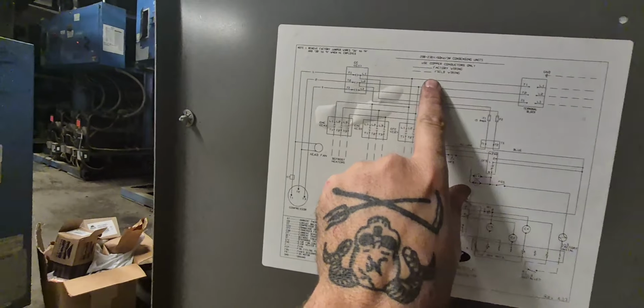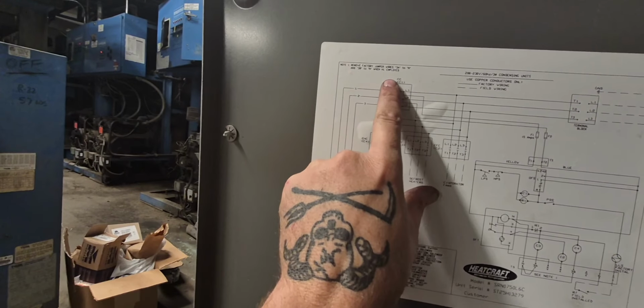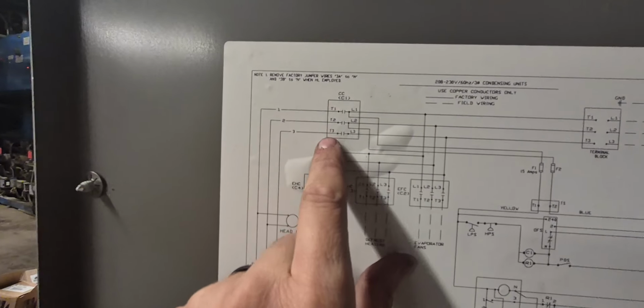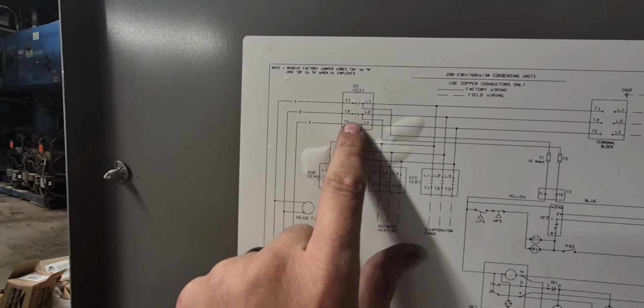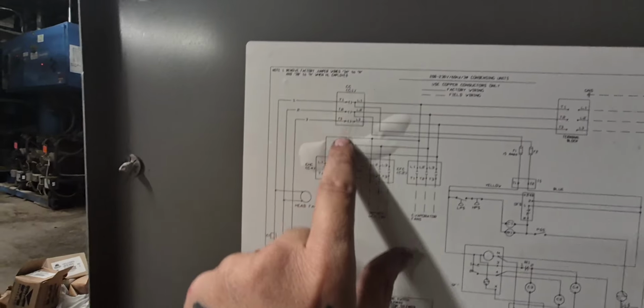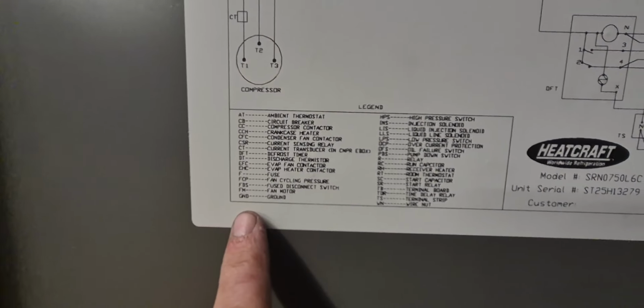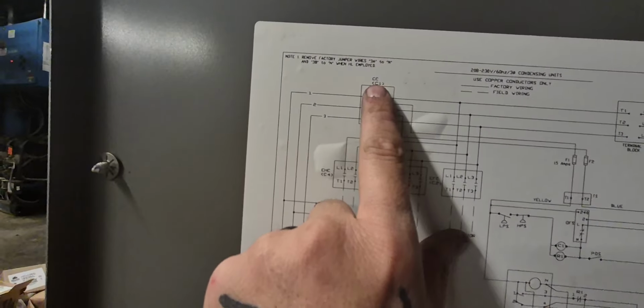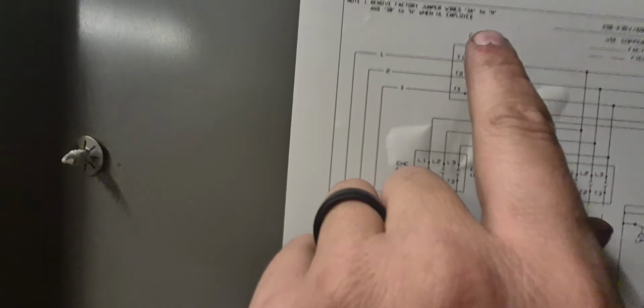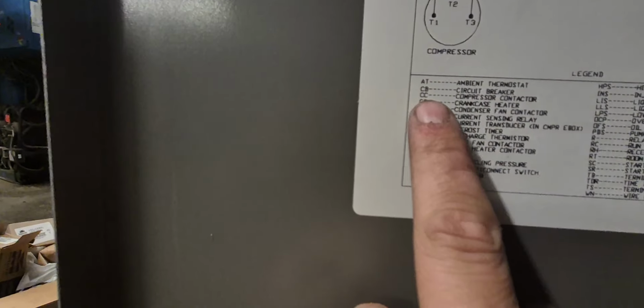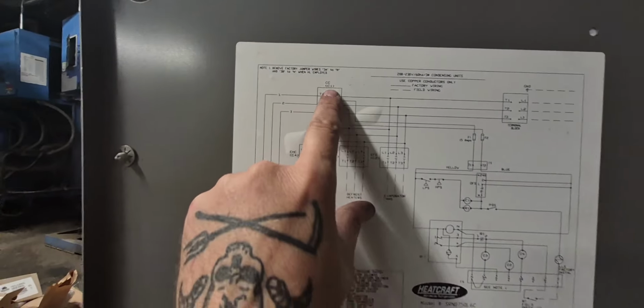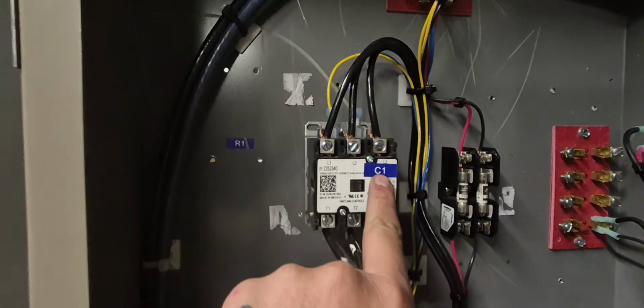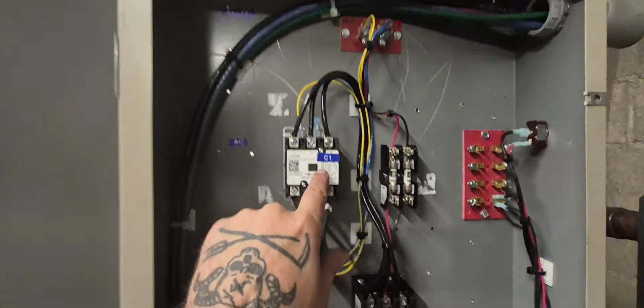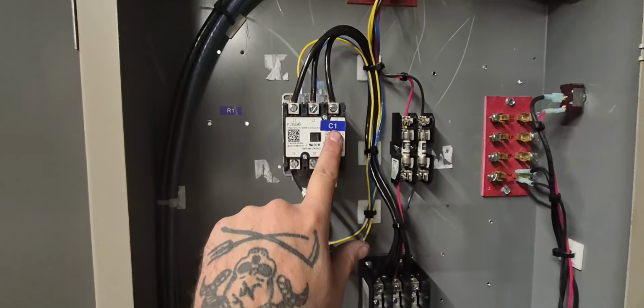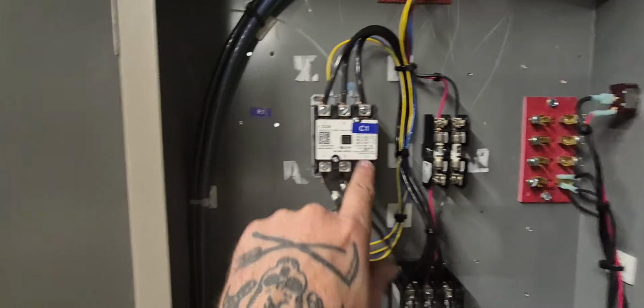And then if we follow those lines out, it shows it goes into CC1. So what does that mean? You can see we have 3 normally open points, but with most of these schematics, you have a legend. So if we look at CC, it stands for compressor contactor, and you can see it's labeled C1, and over here that's labeled C1 too. Now, are all units going to have this? Absolutely not, most that you see probably aren't. This is a new one, so it's still labeled.